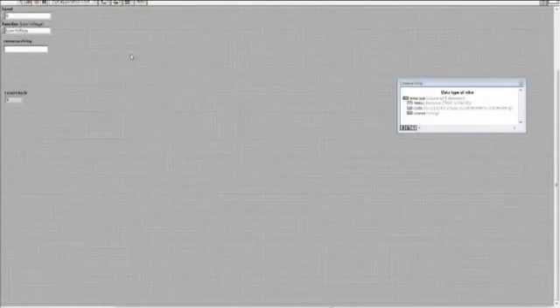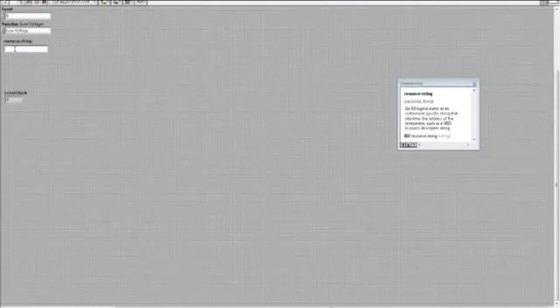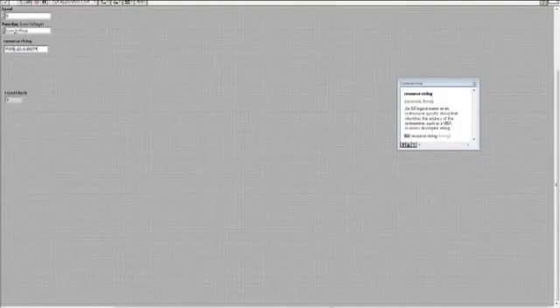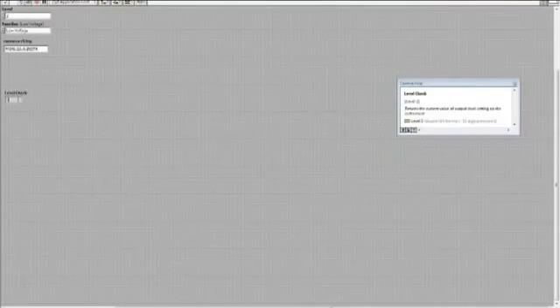Now let's look at the front panel. I rearranged things a little bit — I moved the resource string down and renamed the level indicator to 'Level Check' so I don't get confused between where I'm setting the level and where I'm checking the level. Before we run the program, we need to put in the VISA address in the resource string — you can find this in IO Libraries Connection Expert. I'm going to paste that in, set the level to 2 volts, and set the function to low voltage. Now I'll click Run — and as you can see, Level Check shows 2 volts as well, so I know it got set correctly.